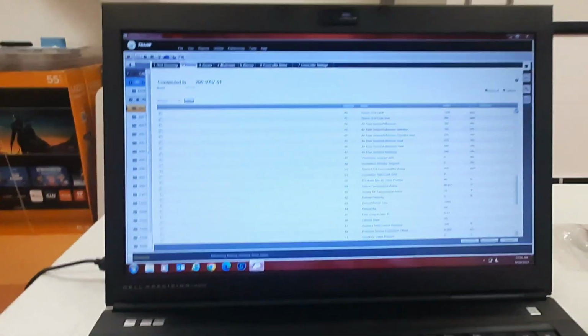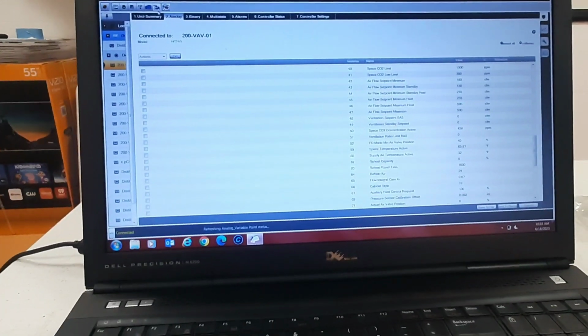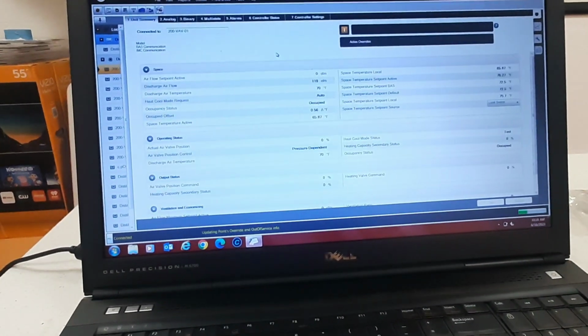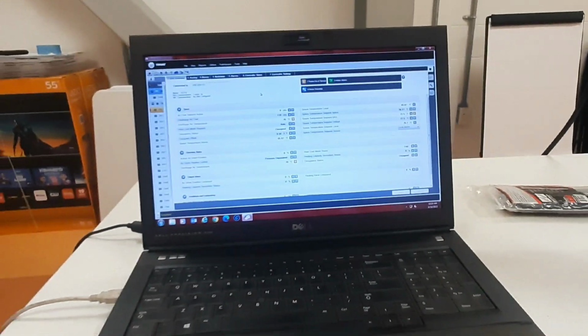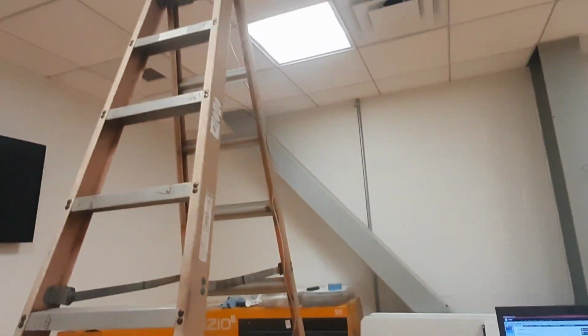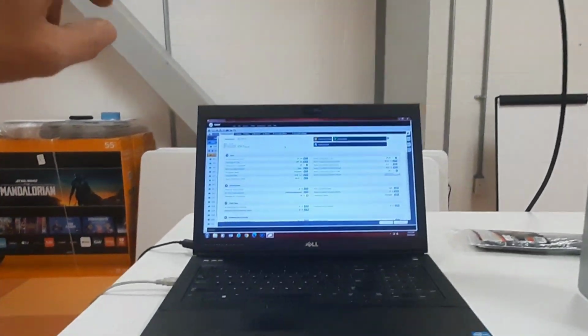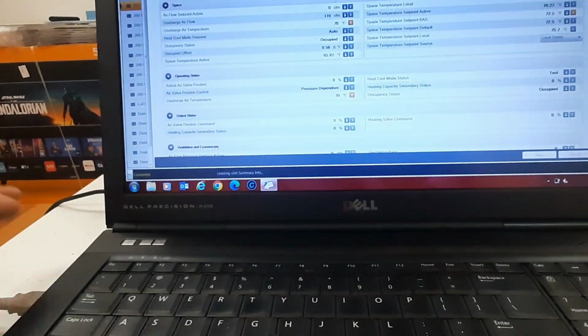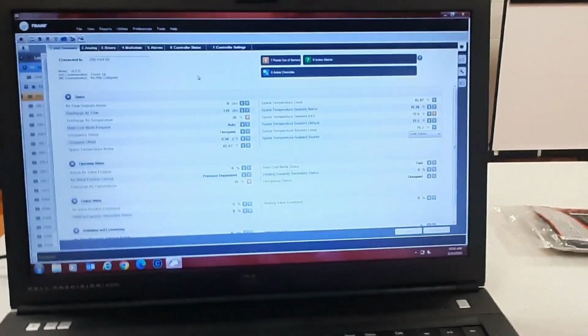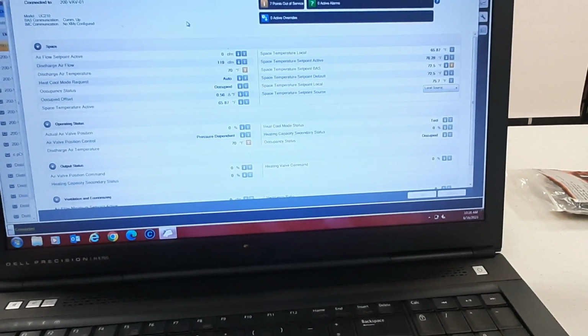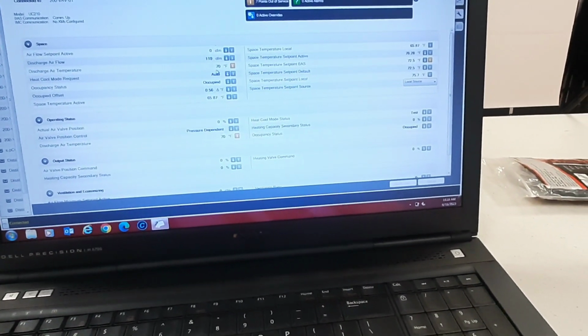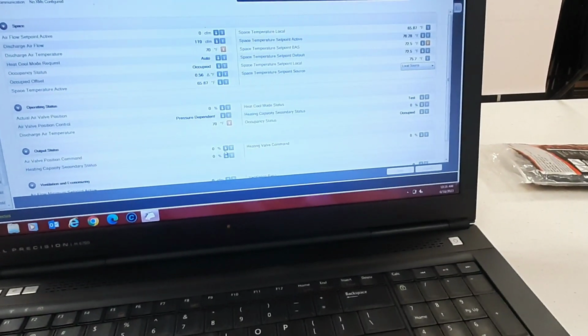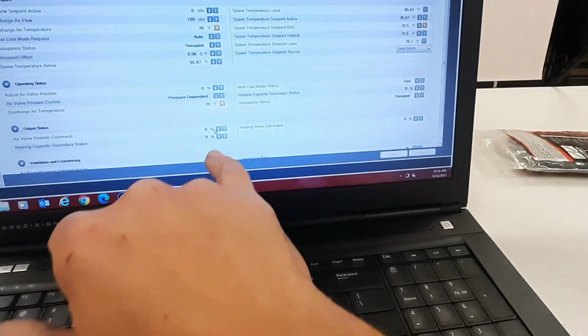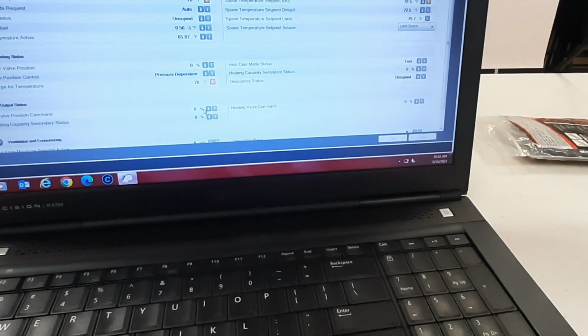Still not getting it to respond, so still working on why it's not responding to me. I'm gonna maybe try a reset. Just pull the power and make sure everything comes back online. I'm not really sure what's going on right now. Like I said, I've been able to override this before to 0 on the air valve position command, but it didn't take when I set it at 100.